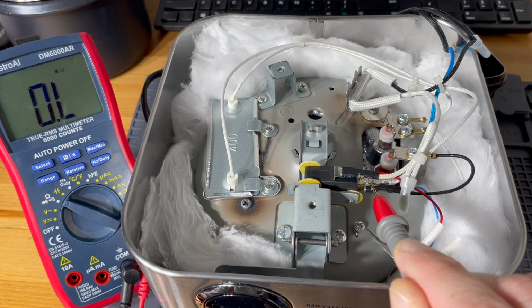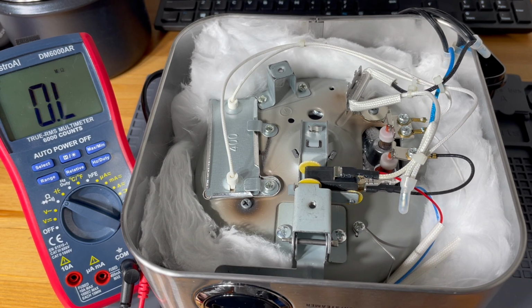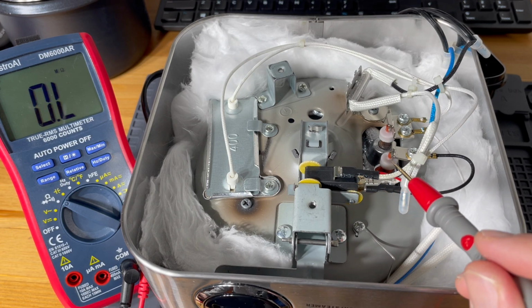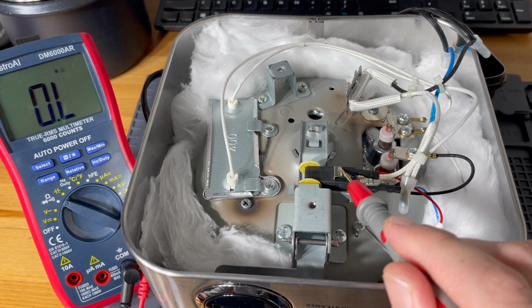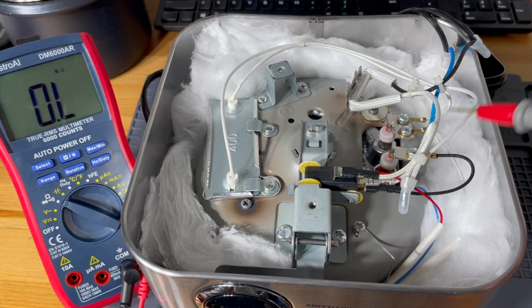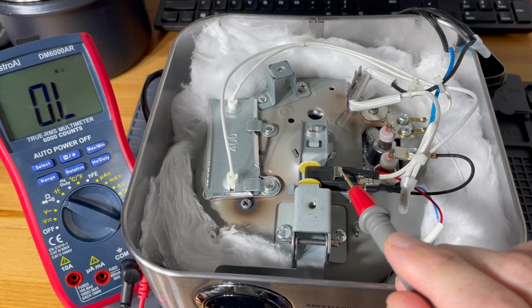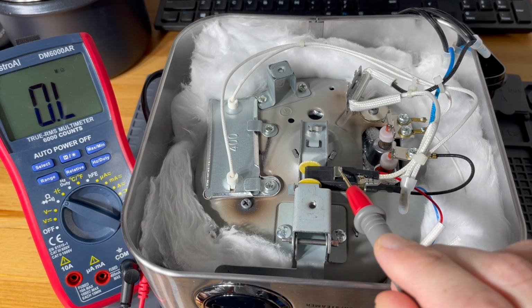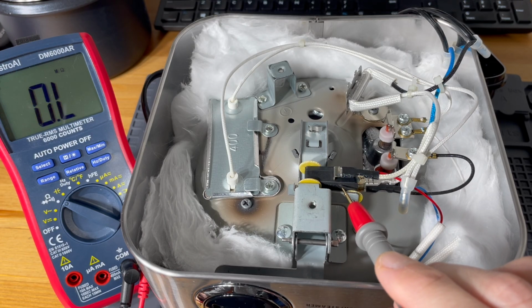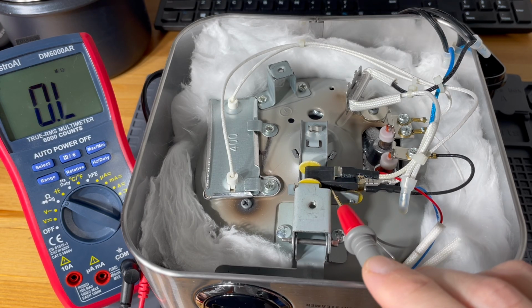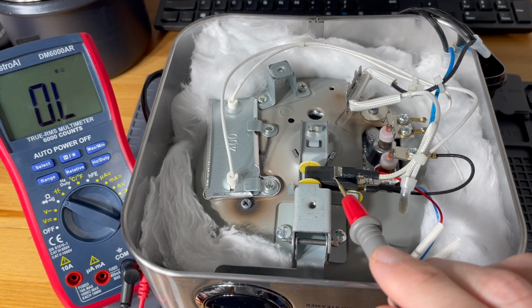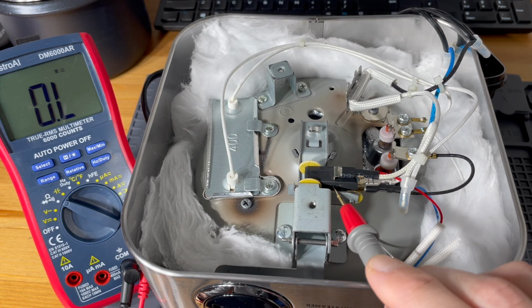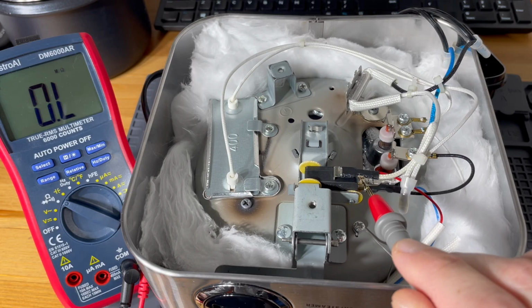And that could mean two things, right? One is that the 120 volts is getting broken somewhere on the wiring on the way to the switch itself, so we're not even getting 120 volts here. Or it could mean that the switch itself has failed, and we are getting 120 volts here, but the switch isn't enabling 120 volts to get here.